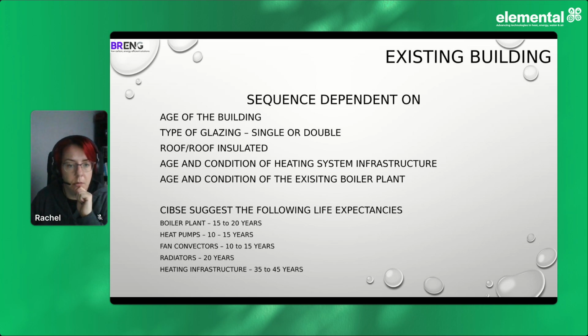We also look at what's the existing system, what's the condition of it. So we've looked at some jobs in the past where the infrastructure's about 10 years old. The CIBSE recommend that radiators and infrastructure should last between 20 and 40 years, realistically. So is the infrastructure good enough to reuse? If so, we then look at what boiler plant do we need to change. Without going into too much detail, which we'll cover in a few more slides, you look at the age of the plant. If the plant is quite new and the infrastructure is quite old, you can actually start decarbonising by doing a sequence of renewing the infrastructure in the building, but allow it to run at a lower temperature, ready for heat pumps. But running at a lower temperature allows you to reduce carbon at that point.